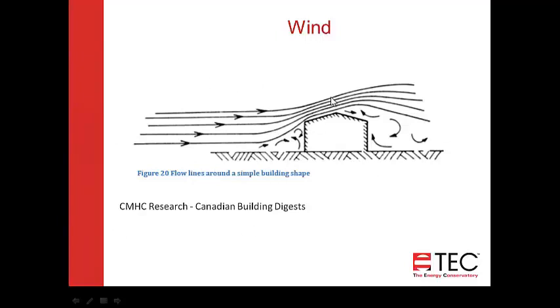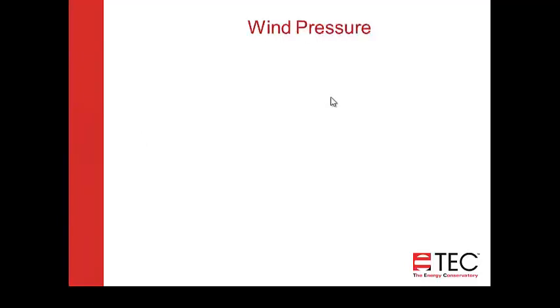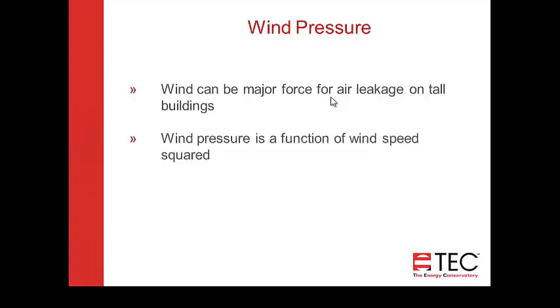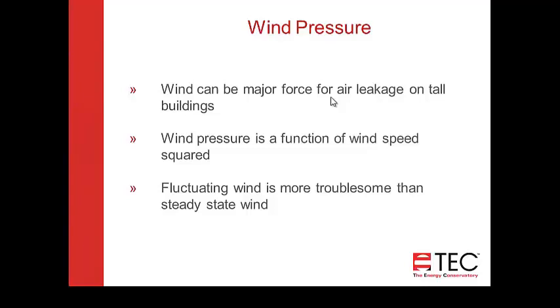This picture came from research done by CMHC and is in the Canadian Building Digest. Wind pressure is definitely a major force for air leakage on tall buildings — we see much higher wind pressures in tall buildings. Wind pressure is a function of wind speed squared, so as wind speed increases, pressures go up dramatically. Fluctuating wind is more troublesome than steady-state wind. With gusting winds, we can see pressure differences of 40 to 50 pascals from one side of a building to another.